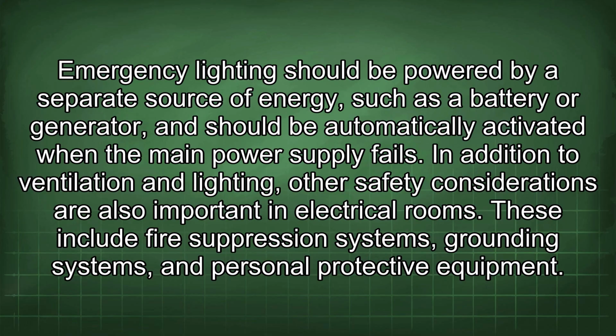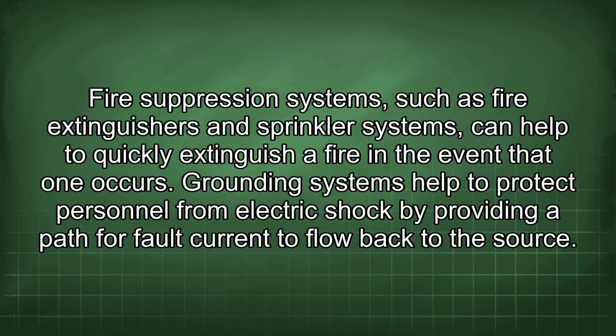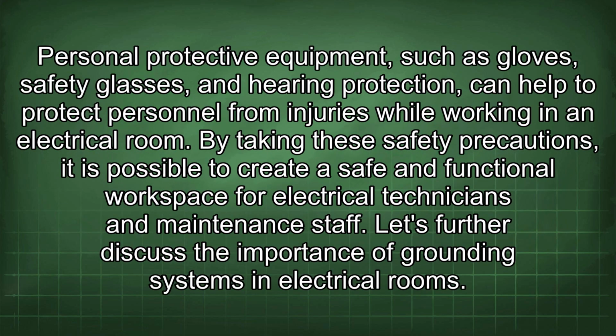In addition to ventilation and lighting, other safety considerations are also important in electrical rooms. These include fire suppression systems, grounding systems, and personal protective equipment. Fire suppression systems, such as fire extinguishers and sprinkler systems, can help to quickly extinguish a fire in the event that one occurs. Grounding systems help to protect personnel from electric shock by providing a path for fault current to flow back to the source. Personal protective equipment, such as gloves, safety glasses, and hearing protection, can help to protect personnel from injuries while working in an electrical room. By taking these safety precautions, it is possible to create a safe and functional workspace for electrical technicians and maintenance staff.